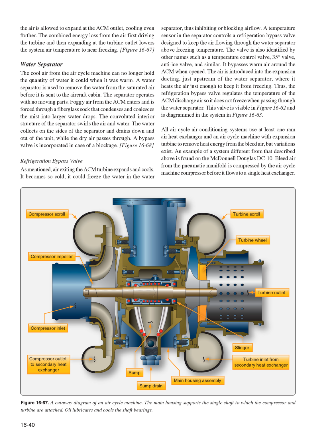Figure 1668, refrigeration bypass valve is mentioned. Air exiting the ACM turbine expands and cools. It becomes so cold, it could freeze the water in the water separator, thus inhibiting or blocking airflow. A temperature sensor in the separator controls a refrigeration bypass valve designed to keep the air flowing through the water separator above freezing temperature. The valve is also identified by other names such as a temperature control valve, 35 degrees valve, anti-ice valve, and similar.